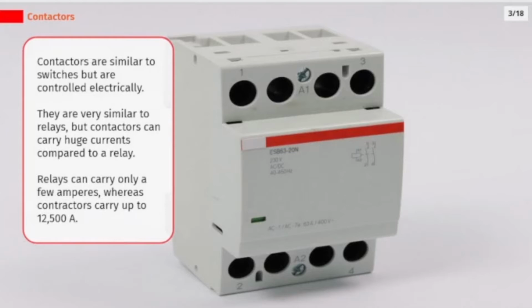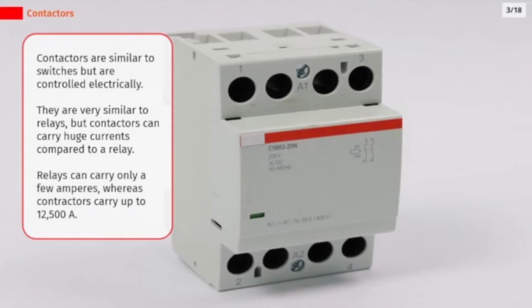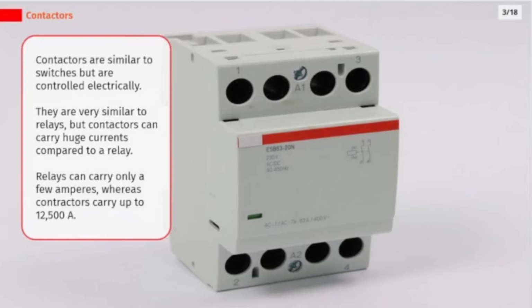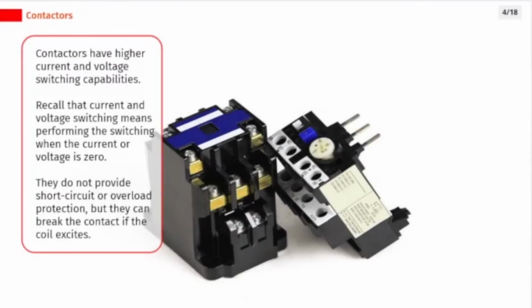Contactors are similar to switches but are controlled electrically. They are very similar to relays, but contactors can carry huge currents compared to a relay. Relays can carry only a few amperes, whereas contactors carry up to 12,500 amperes. Contactors have higher current and voltage switching capabilities. Recall that current and voltage switching means performing the switching when the current or voltage is 0. They do not provide short circuit or overload protection, but they can break the contact if the coil excites.